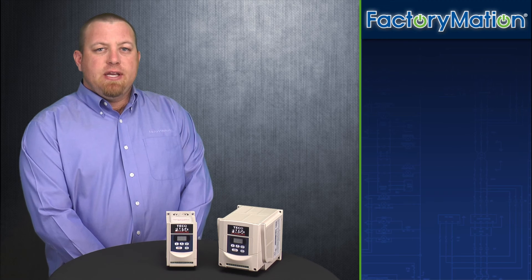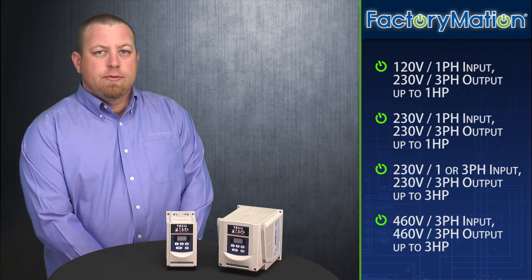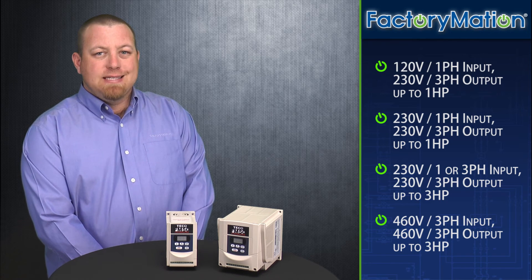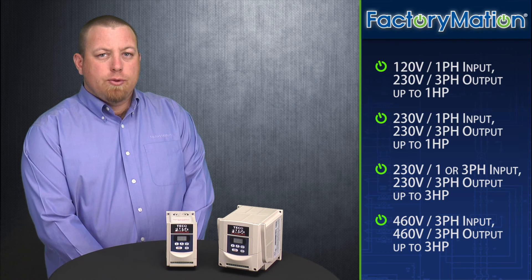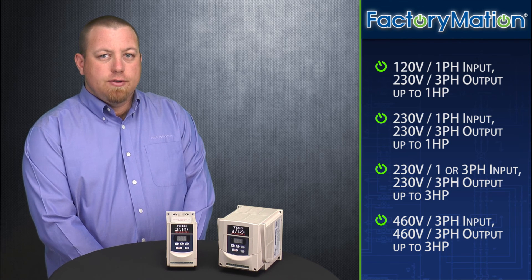The FM50 series VFD is available in four different voltage configurations. First, we offer 120 volt single-phase input to 230 volt three-phase output models for motors up to one horsepower. Second, we offer 230 volt single-phase input to 230 volt three-phase output models for motors up to one horsepower. Third, we offer 230 volt single-phase or three-phase input to 230 volt three-phase output models for motors up to three horsepower. And finally, we offer 460 volt three-phase input to 460 volt three-phase output models for motors up to three horsepower.